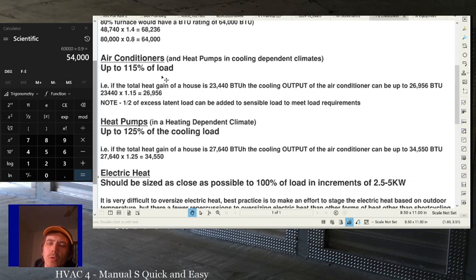So that's on the total BTUs of the equipment, our sensible and our latent together. All right. So if the total heat gain of a house, sensible and latent, was 23,440 BTUs, the cooling output of the air conditioner could be up to 26,956 BTUs. So 23,440 times 1.15 is 26,956. Now for now, I just want you to remember that half of excess latent load can be added to sensible load to meet load requirements. We'll talk about that in a bit, but for now just keep that in the back of your head.